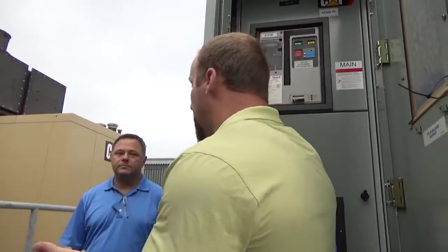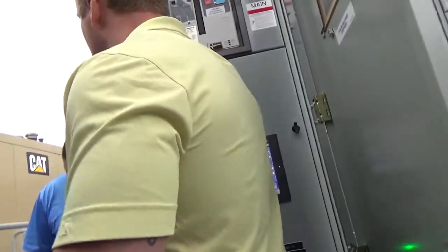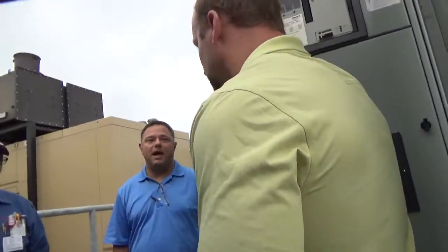That's where Gen Demand can help you if you're a low demand Friday night, where it'll shut that generator down, and you don't have to worry about it when you're busy, when those one or two guys are busy running around the whole site, making sure everything's done. The switchgear is going to handle everything. It's automatic. That's what I'll recommend, because if we don't put some load on it, it's just bad.